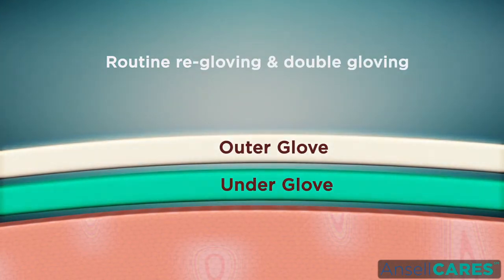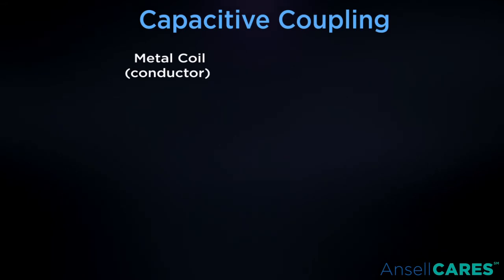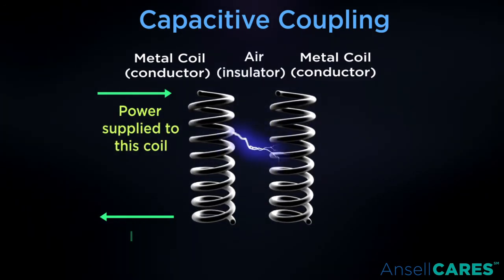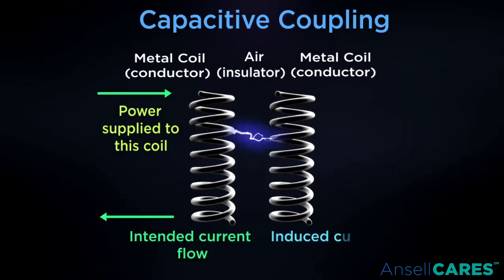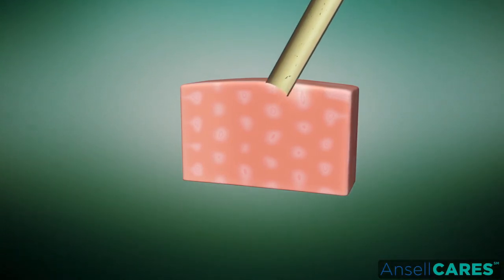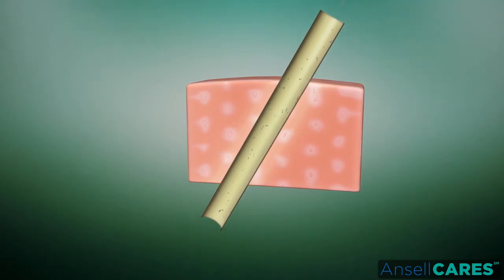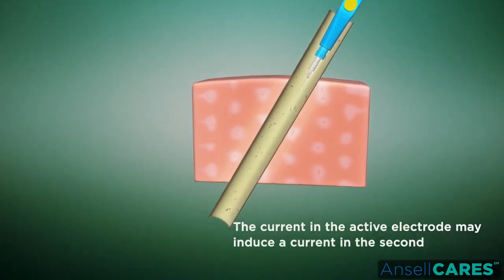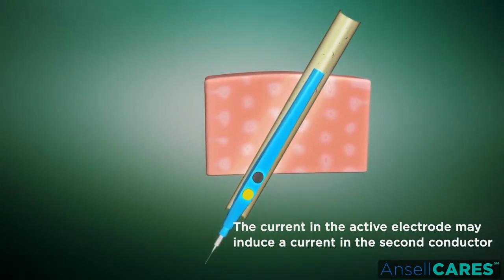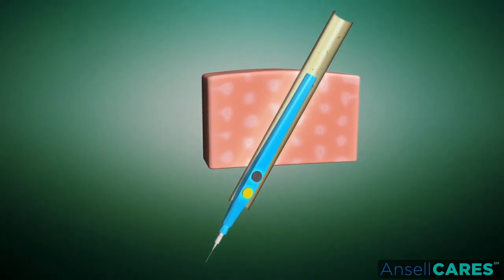Solution: routine re-gloving and double gloving can prevent these problems. Regarding capacitive coupling: capacitance is the ability of two conductors to transmit electrical flow even if they are separated by an intact layer of insulation. Capacitive coupling can occur even when the insulation around the active electrode is intact and the tip of the electrode isn't touching anything metal. If the active insulated electrode is wrapped around a towel clamp, placed inside a metal trocar sleeve, or comes in close contact with any conductive substance for an extended period of time, the current in the active electrode may induce a current in the second conductor. As long as the induced current can dissipate easily through a large surface of tissue, it will not present a problem.